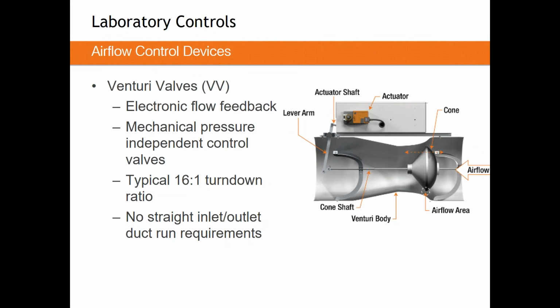If you measure pressure drop across a Venturi valve, you still know nothing about the airflow through that device. Pressure and airflow are in no way, shape, or form mathematically or scientifically linked together. They just aren't. It's not something the manufacturer is keeping from you. They're just not linked. What are linked are the airflow through the device and the position of that internal assembly. So if you'd like more airflow through a Venturi valve, you can adjust what we call the lever arm there on the left, and you can open that valve up a little bit. As you open it up, that position is measured, and it's directly related to an airflow through the device.